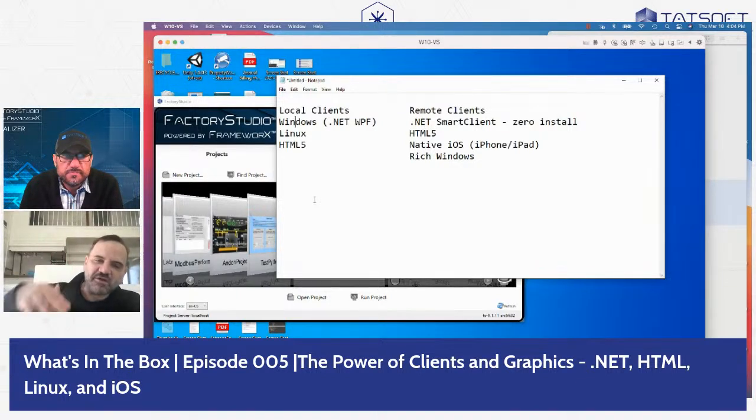But if you are on the factory floor operating a machine, or you are a supervisor or an operator in the control room, you click anything in any display in an HMI, SCADA, or supervisory, and if it takes more than 100, 200 milliseconds for them to see some reaction to their action, they will start to look badly on that system.